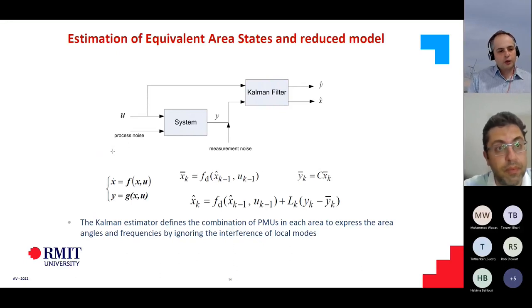To find those dynamics, we found that integrating a Kalman estimator with a reduced model would be the perfect way, because then we have both the reduced model and the measurements coming from a single model. The Kalman filter combines all of them, the measurements coming from the network, from the PMUs, together with the model we developed as the reduced model, giving us a very good estimate of different states of the system.